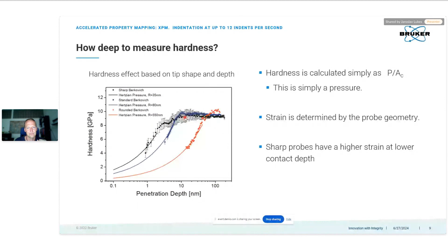So if you want to reach very high resolution on your hardness map, it's also beneficial to have a very sharp probe, because then you can produce small indents, produce the high stresses right from the beginning, and then you can pack the indents close to each other and reach the high resolution in your hardness map. So if you do all this, think about indent spacing and your indentation depths, and you have nice and sharp probes, then you can do very interesting and nice studies on different materials over even larger scales. You can really go from a micro scale to hundreds of micron scale.